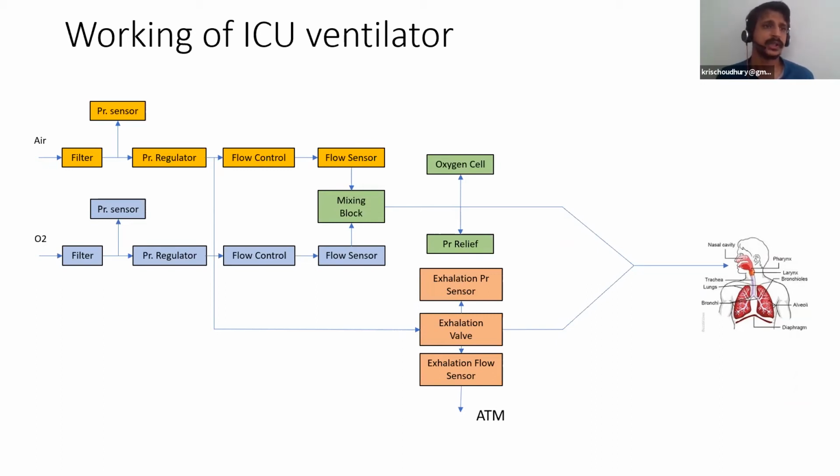So this pressure relief always ensures that if the software has a bug or the electronics have malfunctioned, or any of the valves have malfunctioned, it basically releases all the pressure and gives only what is acceptable to the patient. And no surgeon or doctor can even get access to this valve, nor is it settable by them. So from here it goes to the patient, and then the patient inhales and exhales these gases.